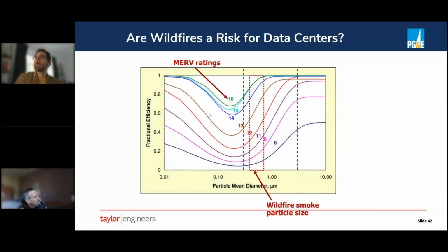So speaking of that kind of risk, one of the things that we certainly have to deal with here in California is wildfires. And what is the risk to a data center from wildfires if you are using outside air to cool your data center? So this slide shows the filtration efficiency at different particle sizes of different filter ratings, right? And so I said before, you should have at least a MERV 13. We're usually using even MERV 15. And wildfire smoke happens to be in this range, typically, particle size. And you can see, for example, at a MERV 15, you've got an efficiency of 80 to 90%. And so most of the particulates, but not all, are going to get filtered out.